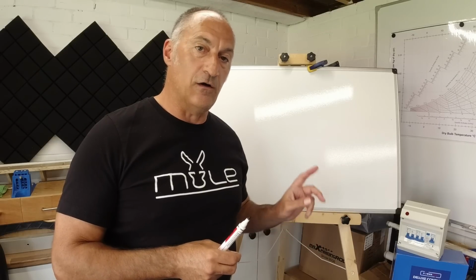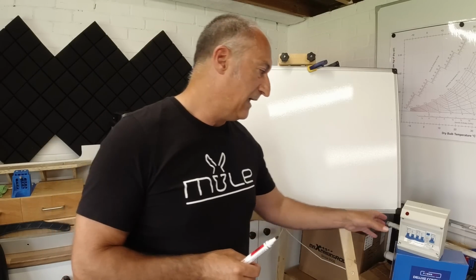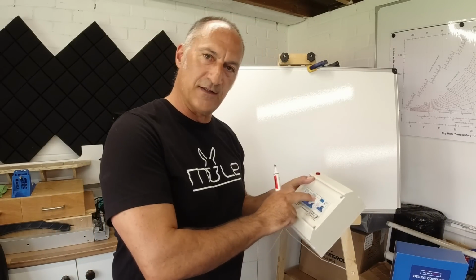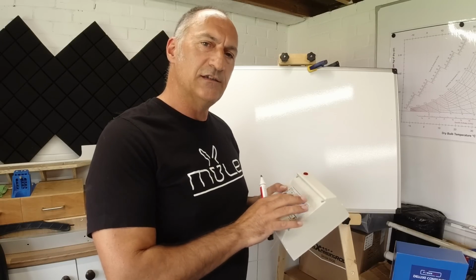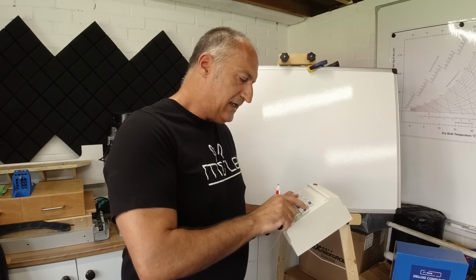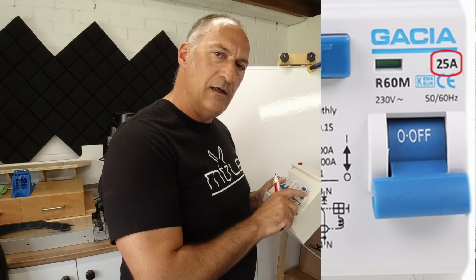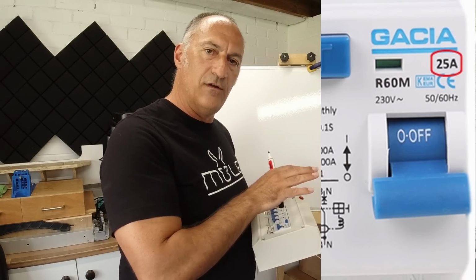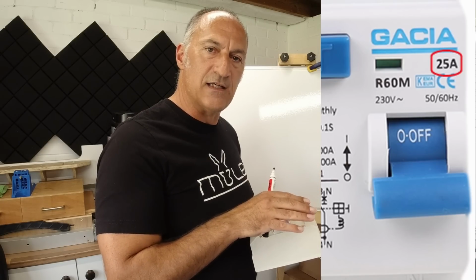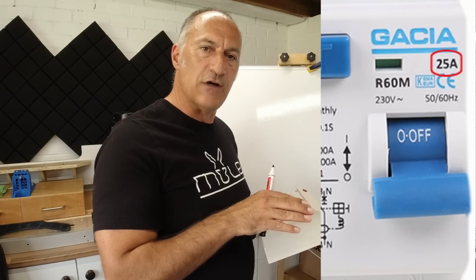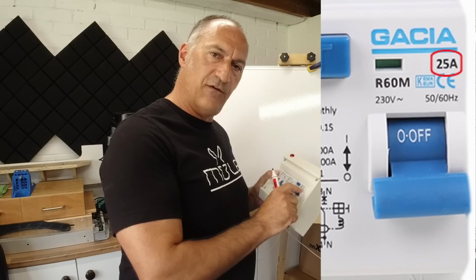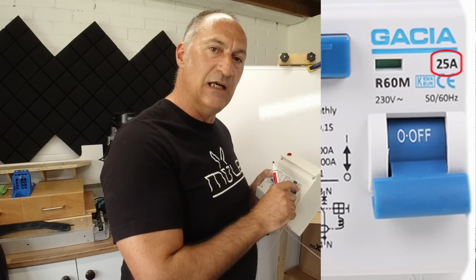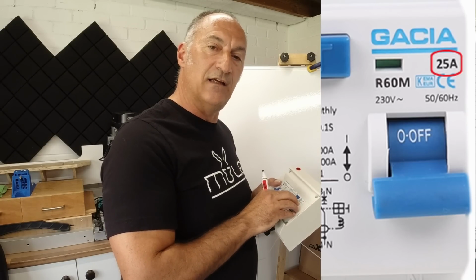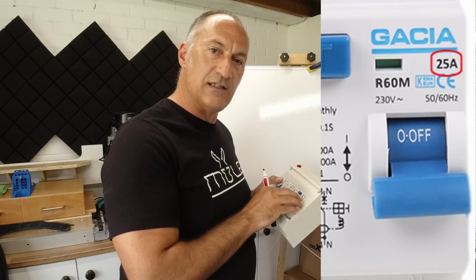So just to summarise, there's a few key things that you need to look out for when you're purchasing your RCDs and MCBs, and some of the small text on the front here is quite important. So let's just look at that. The RCD here has got a rating of 25 amps. Now, as we've seen before, that's not the overcurrent protection rating. It won't act like a fuse or a trip. So this 25 amp rating on this RCD is purely the switch rating of the contacts within inside this device.